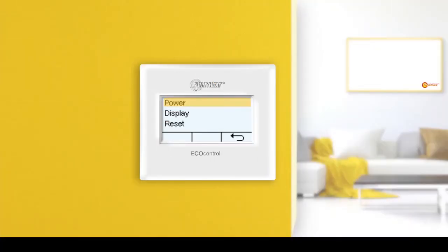What is the power menu? In the power menu, you can enter the power of the Sunny Heat infrared heater that is controlled by this EcoControl thermostat. If several Sunny Heat infrared heaters are controlled with EcoControl, the power of the Sunny Heat infrared heaters must be added to see the correct energy consumption. The power is indicated on the type plate of the respective Sunny Heat infrared heater. It can be found behind the term power and is indicated in the unit watt.